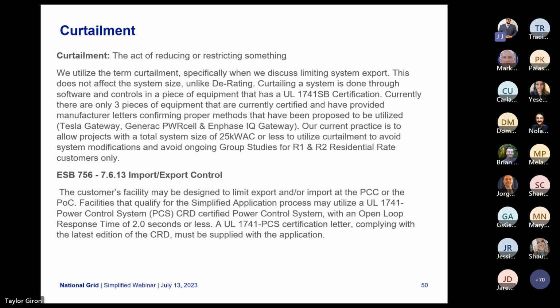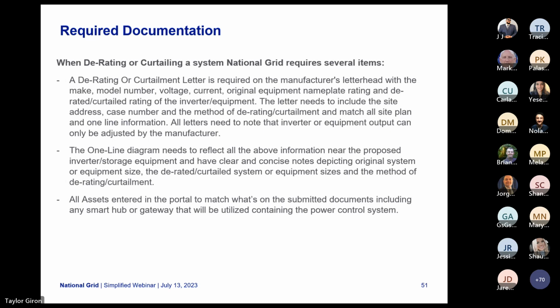Next slide, please. When someone is going to be utilizing derating or curtailment as part of their system, we're going to require several additional items. The first one being a derating or curtailment letter on a manufacturer's letterhead. This letter, specifically for the equipment, has to include the make, the model number, the voltage, the current, the original nameplate rating of that piece of equipment, and the curtailed rating of the inverter or piece of equipment that is being proposed to be utilized for that system.